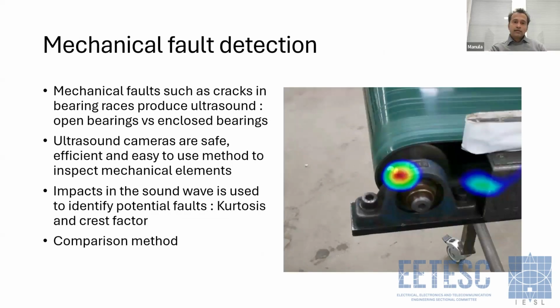Yes, so with that, we can move into our next application, which is mechanical fault detection. Up to now, we have discussed partial discharge detection and leak detection with acoustic cameras. Our third application is mechanical fault detection. This is a relatively new field for acoustic cameras, but it still has good potential to detect mechanical faults, maybe at a very early stage, as I said earlier. Mechanical faults such as cracks on bearing races, in the inner race or outer race. Those tiny cracks would produce ultrasound at the early stage of the failure.